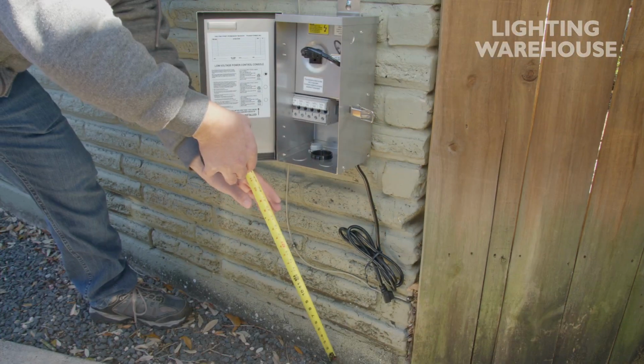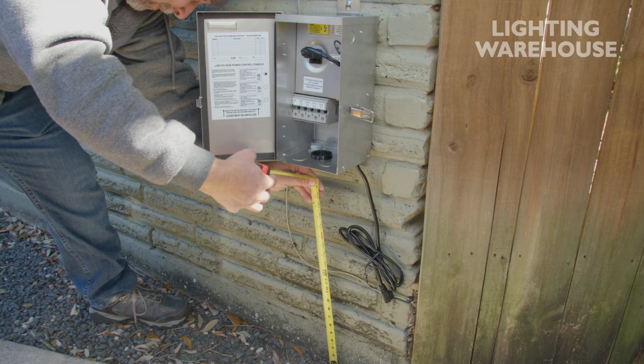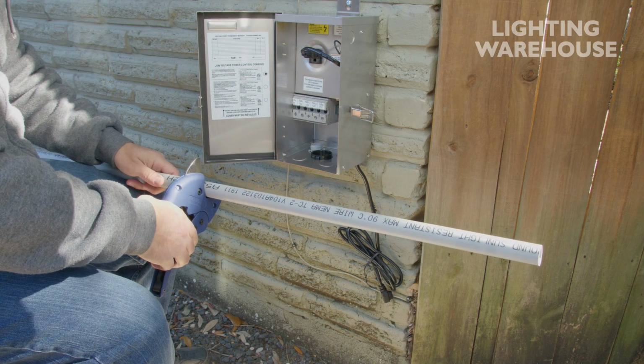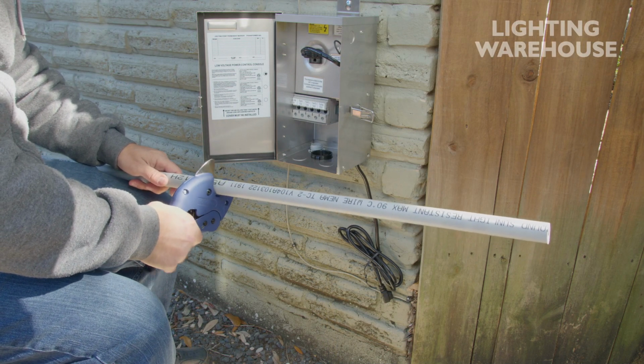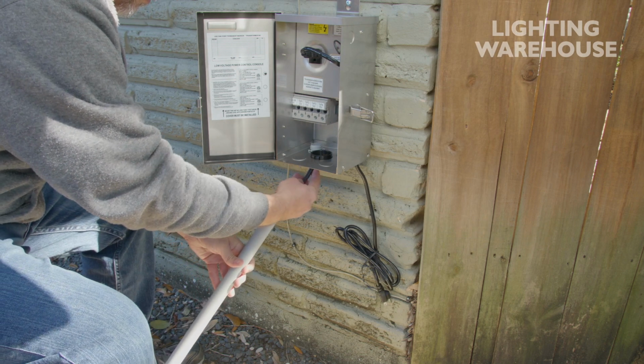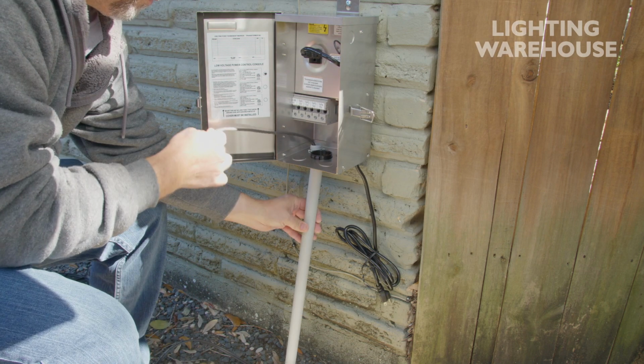By law, the bottom of the transformer has to be at least 12 inches above grade. But low to the ground is really difficult to work with, so we recommend you put it somewhere around waist height or chest height. Once it's mounted, measure from the ground to the terminal adapter, then cut the conduit accordingly. Run the end of the wire through the conduit and into the transformer. Then put the conduit in place. Now your transformer is set.